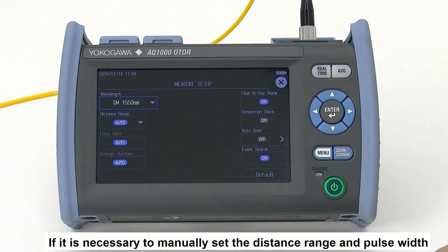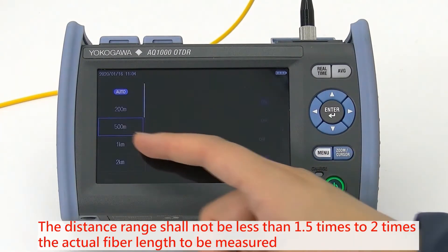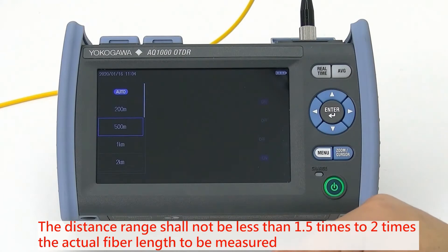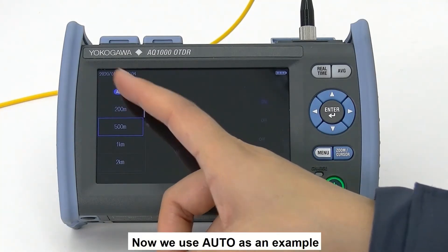If necessary to manually set the distance range and pulse width, the distance range should not be less than 1.5 to 2 times the actual fiber length to be measured. Now, we use the auto as an example.